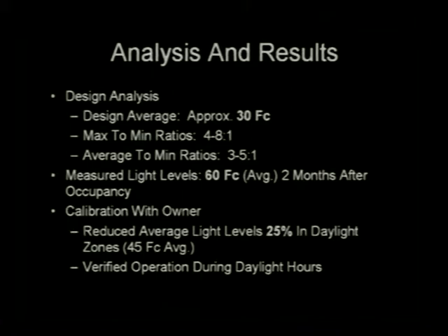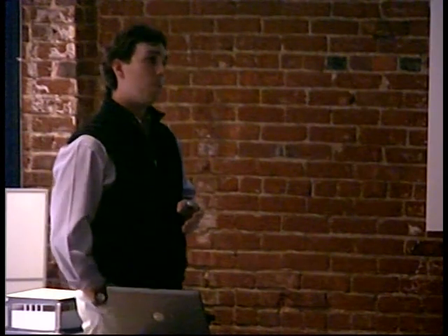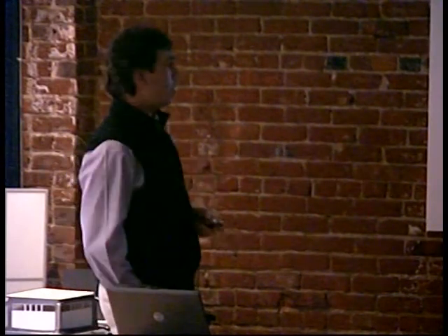And so we were very nervous when we saw that happen very early on in the morning, but once the sun got up over the canopy of the building, the system operated properly. One of the things we found out about that, we would probably implement shrouds of some sort on our sensors in those applications from here on out to minimize that effect of abnormal conditions, given the height of the building and where we are in relation to the horizon.